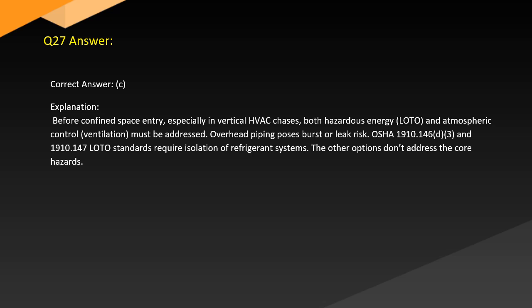Answer. Correct answer: C. Explanation. Before confined space entry, especially in vertical HVAC chases, both hazardous energy (LOTO) and atmospheric control (ventilation) must be addressed. Overhead piping poses burst or leak risk. OSHA 1910.146 D3 and 1910.147 LOTO standards require isolation of refrigerant systems. The other options don't address the core hazards.